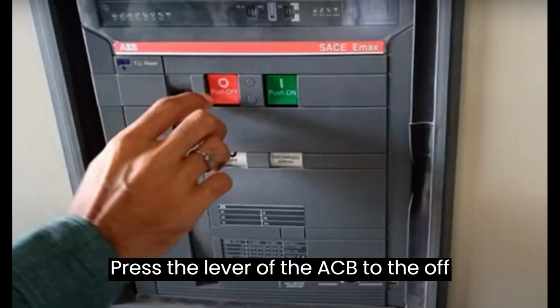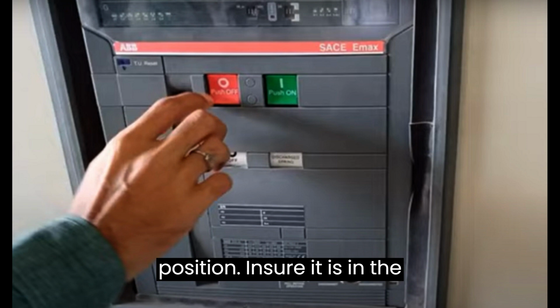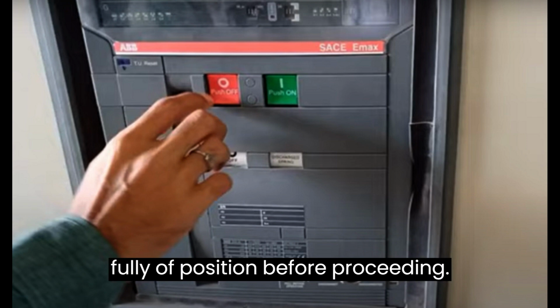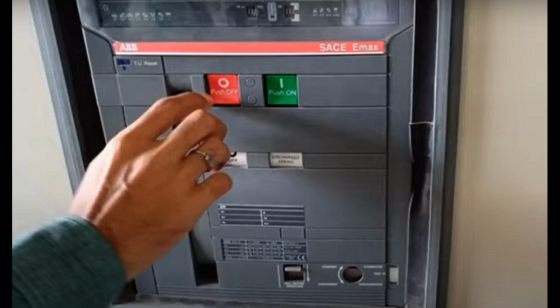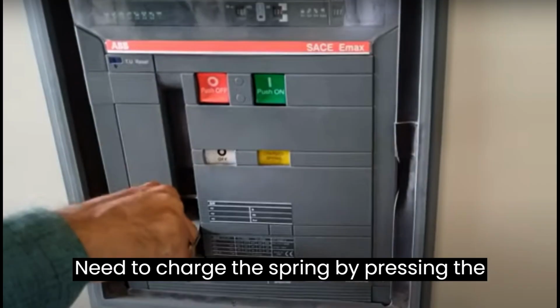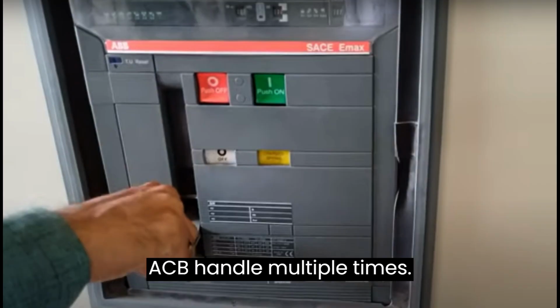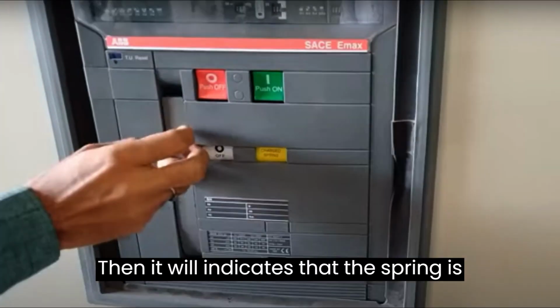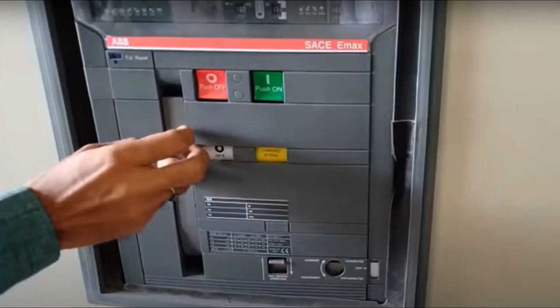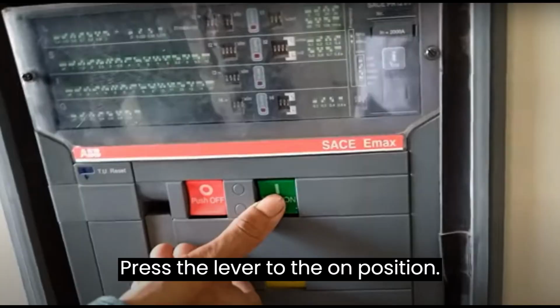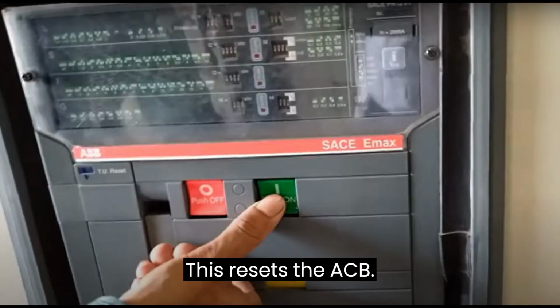Press the lever of the ACB to the off position. Ensure it is in the fully off position before proceeding. You need to charge the spring by pressing the ACB handle multiple times. Then it will indicate that the spring is charged by yellow color. Press the lever to the on position. This resets the ACB.